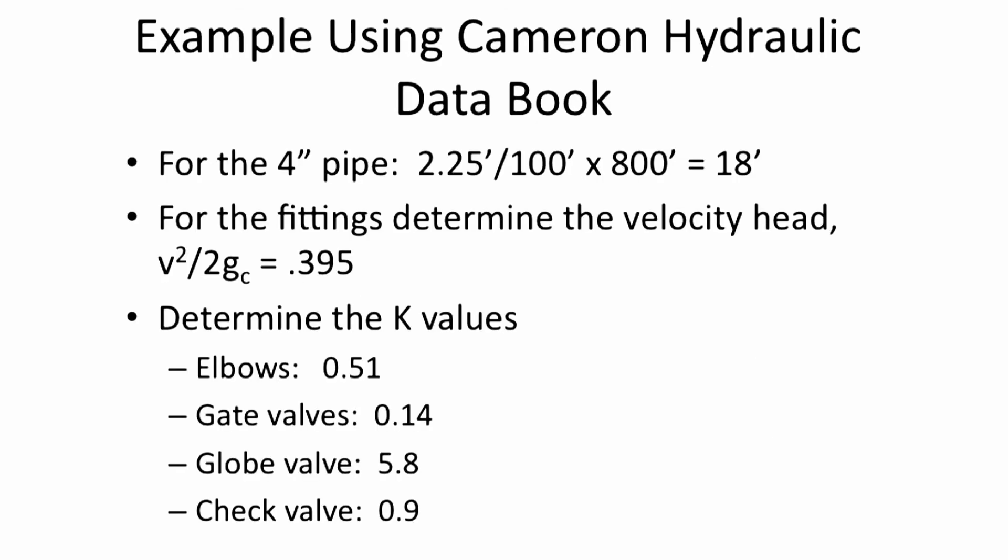From the book, for a 4-inch new steel pipe at 200 gallons per minute, the friction loss is 2.25 feet per 100 foot of pipe. So you multiply this by the 800 feet of pipe, and you have 18 feet of pressure drop.